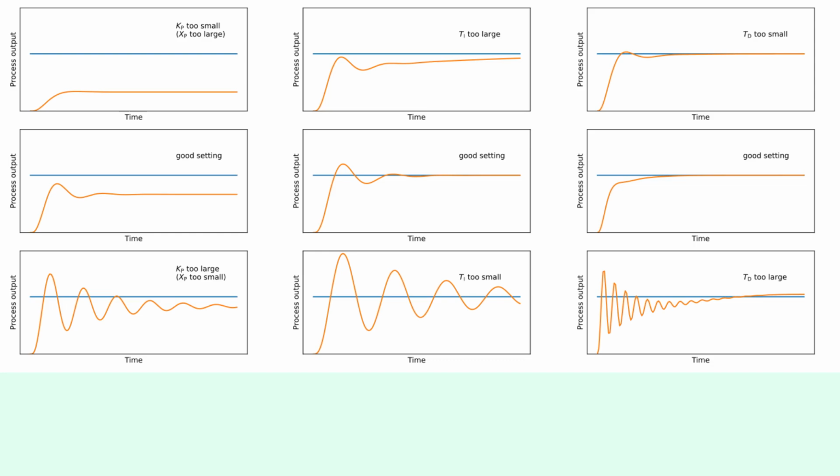Technicians often use trial and error or Ziegler-Nichols methods to find the right settings. Today's digital controllers even include auto-tuning algorithms, making the process faster and more accurate. When tuned correctly, a control system maintains ideal comfort with minimal energy use, the ultimate goal of HVAC automation.